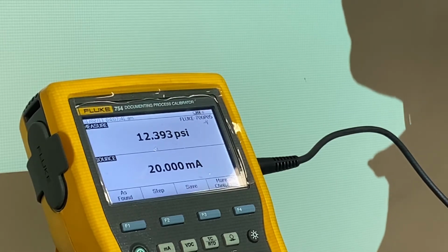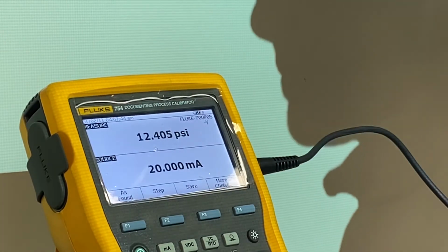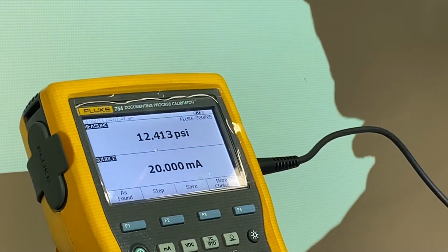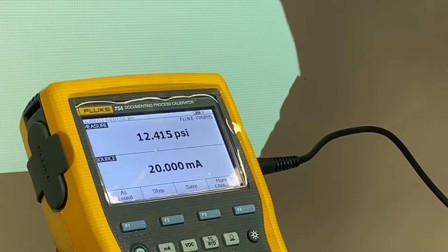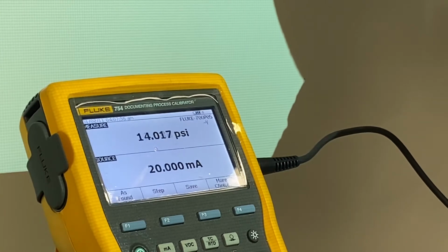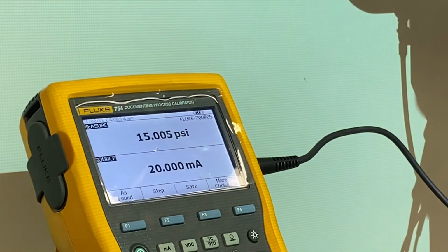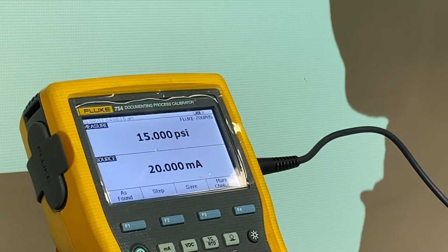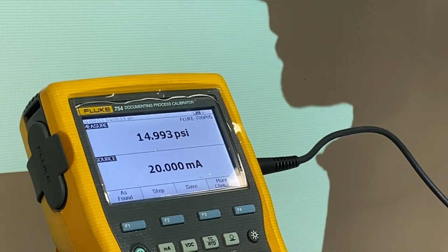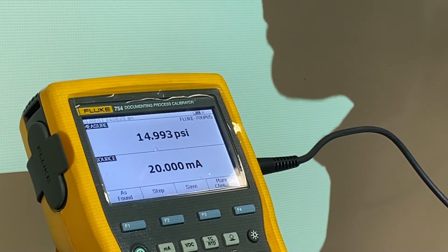And as you can see, we're still well above our expected value. So we're going to adjust our span until we reach 15 psi at 20 milliamps. And now we are well within tolerance. We are well within plus or minus 0.5% of span on our tolerance.